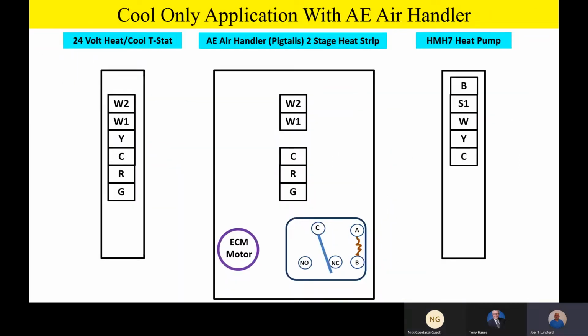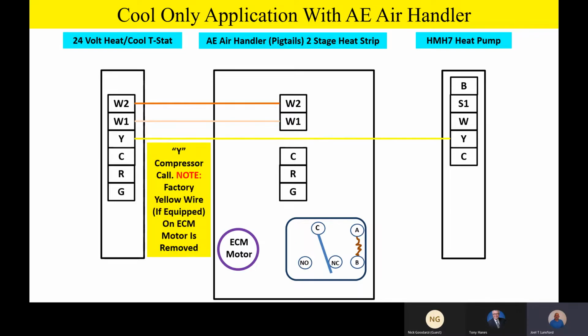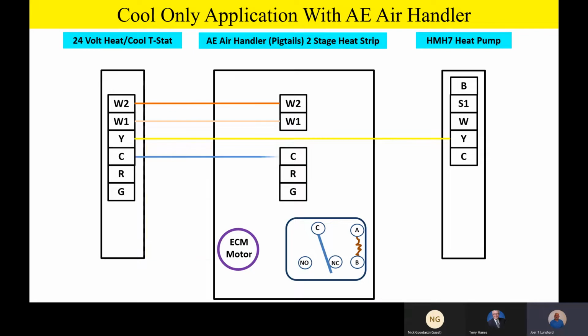All right, so let's talk a little bit about cool only application with an AE air handler. In a cool only application, we're going to tie in our heat strips, W1 and W2. We're not going to take anything outside. Your Y terminal is going to go straight outside. That'll be one of your wires outside. 24-volt common will go all the way through.